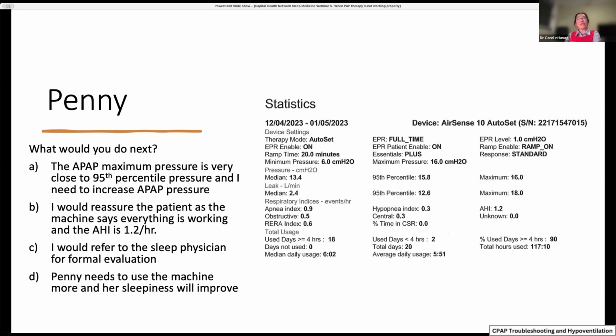You could say, perhaps the maximum APAP pressure is very close to the 95th percentile pressure, and maybe the pressure titration is topping out because we put a limit here of 16. So therefore, just increase the maximum pressure in order to allow the machine to deliver more pressure.